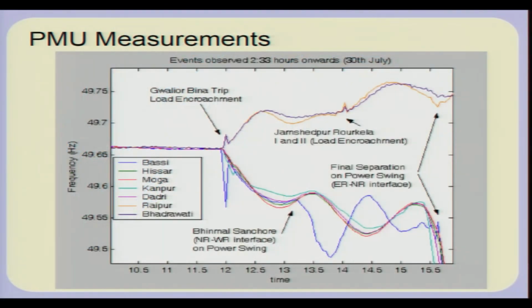One of the reasons for under frequency tripping is that below 47 usually you have larger blade vibrations in a turbine, because the resonant frequencies of the blades get excited in case the frequency falls below 47. So, many thermal generators will actually trip, and this is what happened in the 2012 blackout. You had a system which was integrated, and a certain disturbance caused the phase angular difference between the two parts of the grid to go on increasing. After a point, the separation was so much that the machines could not be brought back.